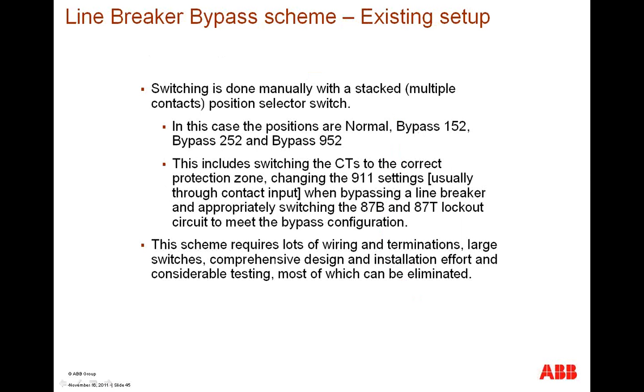So the point we're showing this bypass scheme is that in a traditional application, you need a transfer switch done by a manual stacked switch, switching currents to provide the correct protection element its needed source. In this case, the positions are normal, bypass 152, bypass 252, and bypass 952 on your switch positions.